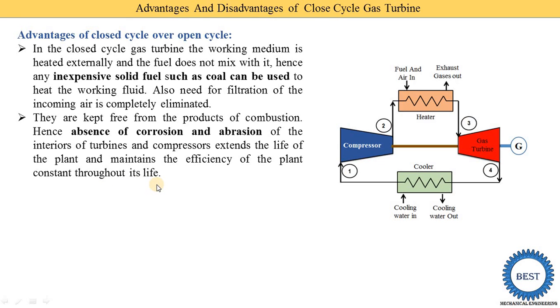In an open cycle, the combustion product is supplied directly into the turbine, so there are chances of corrosion and abrasion on the turbine blades. But in a closed cycle, we are not supplying the products of combustion into the gas turbine. Hence, the absence of corrosion and abrasion extends the life of the plant, maintains efficiency constant throughout its life, and reduces maintenance requirements.